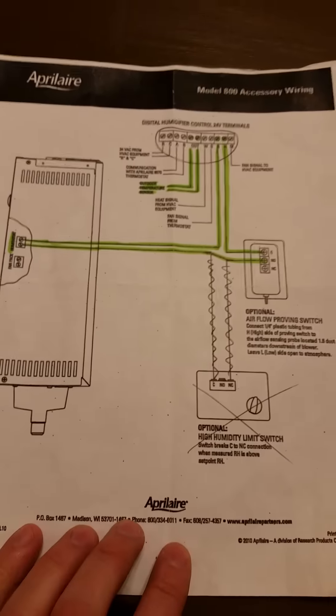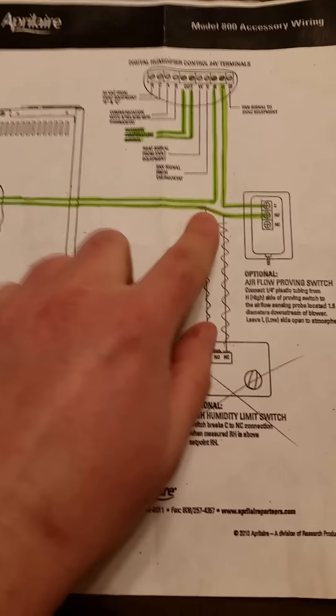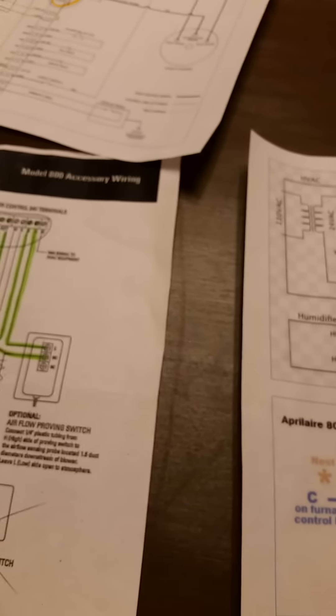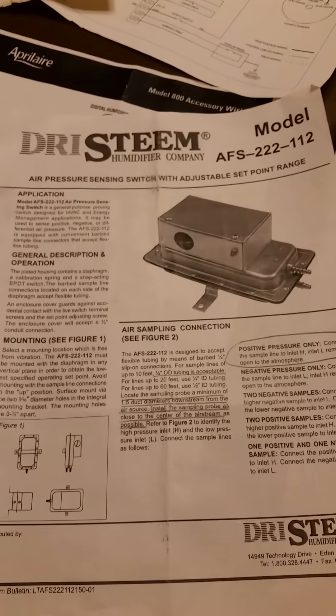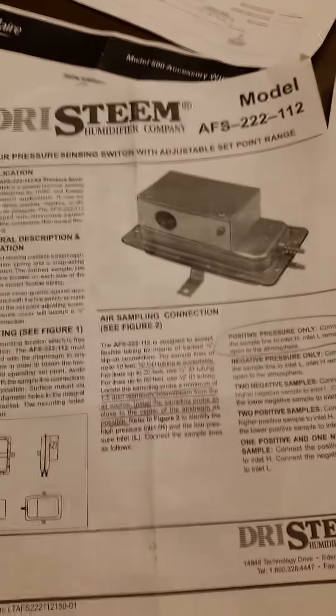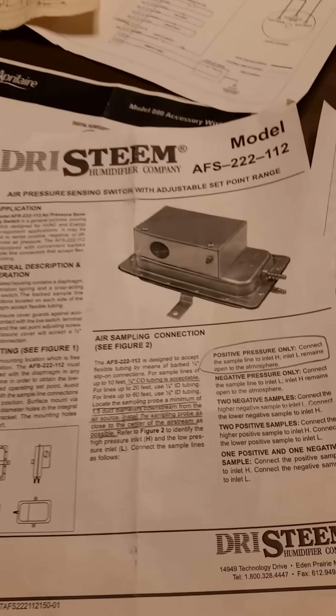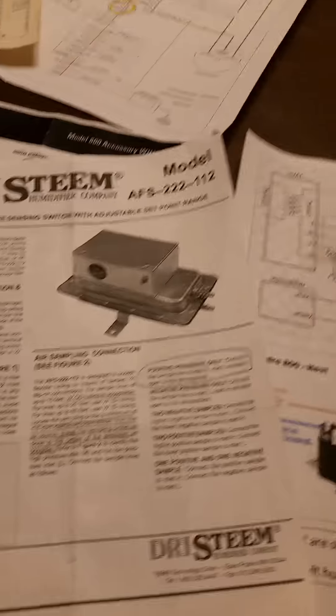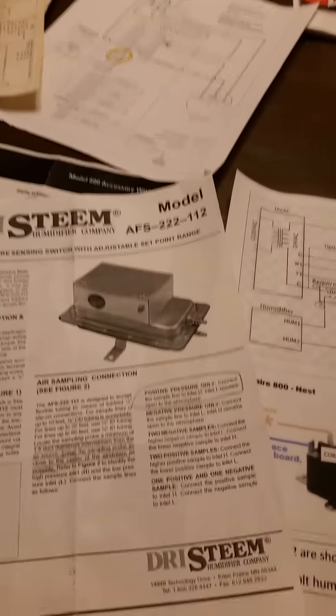I've also included the airflow switch in my setup. The spec for it is the DriSteem model AFS-222-112 — an air pressure sensing switch with an adjustable set point range. It has a high-pressure and low-pressure sensor. The low pressure is exposed to the environment and the high pressure is inserted into the supply duct. When the fan is working, the pressure difference triggers the switch to turn on.